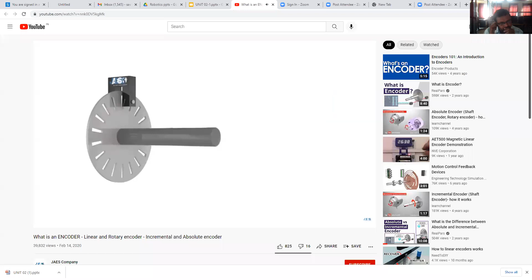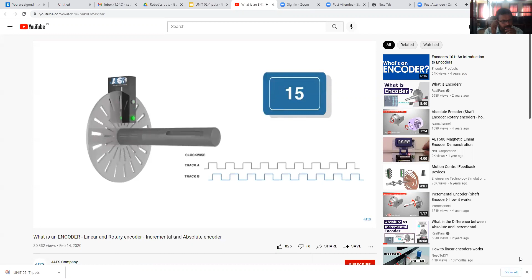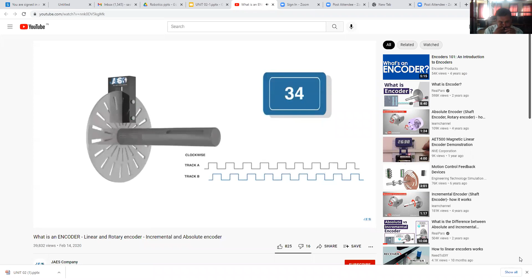The most common type of incremental encoder uses two output channels, A and B, to sense position and direction of rotation. Using two code tracks with sectors positioned 90 degrees out of phase, the two output channels of the encoder indicate both position and direction of rotation. If A leads B, for example, the disk is rotating in a clockwise direction. If B leads A, then the disk is rotating in a counterclockwise direction.